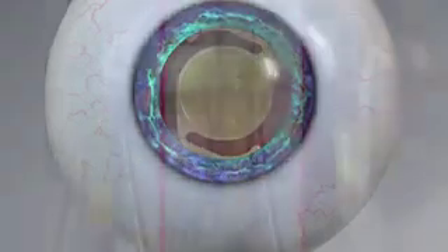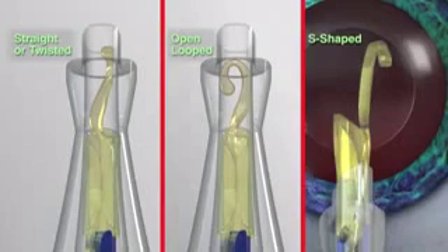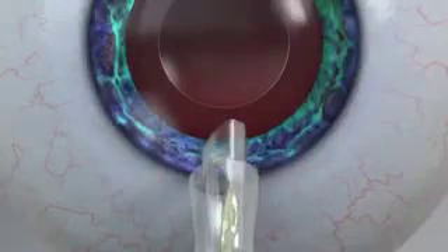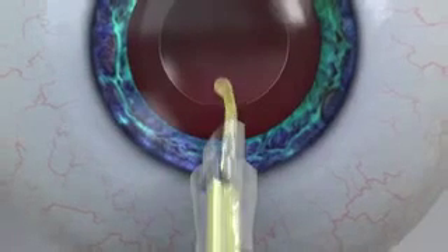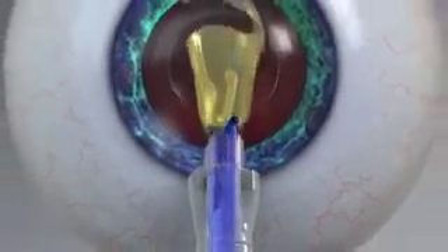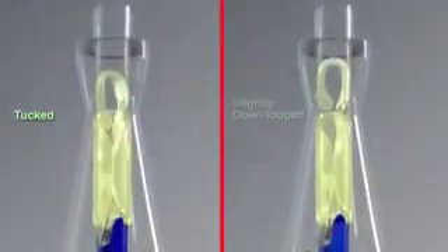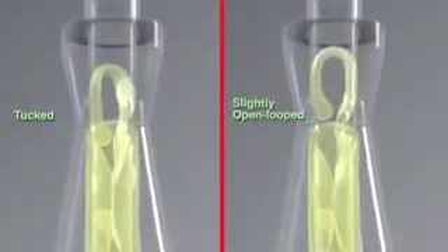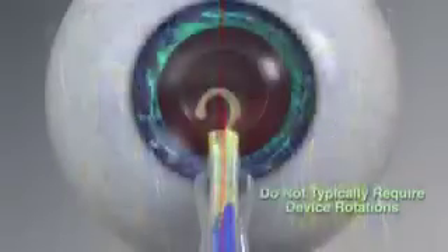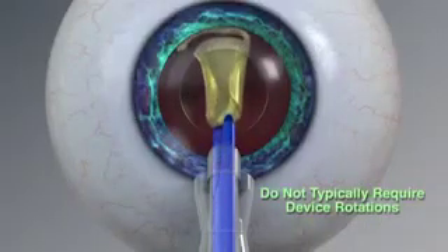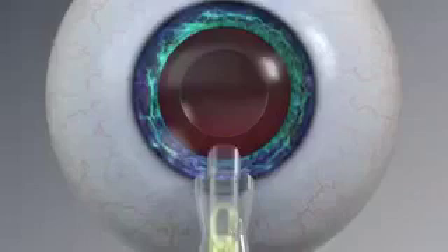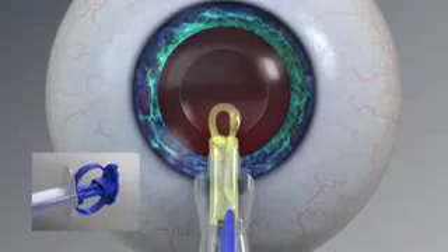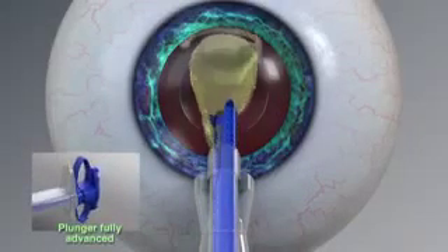In summary, these straight, twisted, open-looped, or S-shaped leading haptic configurations are normal, and the IOL can be delivered by rotating the device as previously described. These tucked and slightly open looped leading haptics are normal leading haptic configurations that do not typically require device rotations. Also notice when much of the trailing haptic is alongside the plunger, it may require fully advancing the plunger to ensure the entire trailing haptic clears the nozzle and the incision.